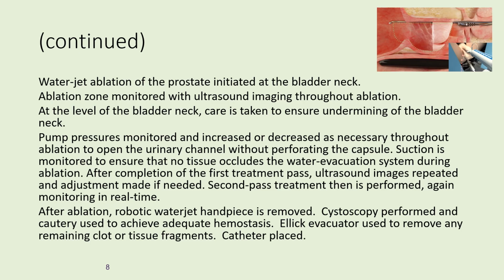At the level of the bladder neck, care is taken to ensure no undermining of the bladder neck. Pump pressures are monitored and increase or decrease as necessary throughout the ablation to open the urinary channel without perforating the prostatic capsule. Suction is monitored to ensure that there's no tissue that occludes the water evacuation system during ablation. After completion of the first treatment pass, ultrasound images are repeated and adjustments are made if needed. Second pass treatment is then performed, again monitoring in real time.